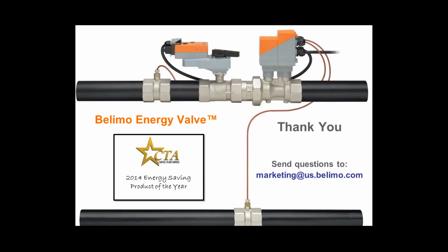Okay. I think I'm going to take two of the questions and combine them. One of the questions was, so the valve consists of a flow meter, 2 temperature sensors, and a BTU meter. And then the next question after that is, is the valve a pressure-independent valve, or do you need additional pressure control strategies for good valve authority? Okay, so I think I may have answered both of these questions a few questions back, but to answer them directly, the energy valve is fully pressure independent on its own. So it doesn't need any pressure devices. It doesn't need a balancing valve.